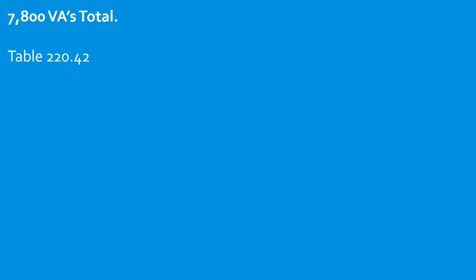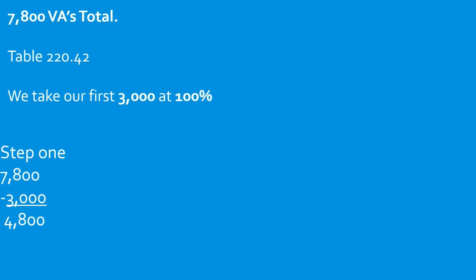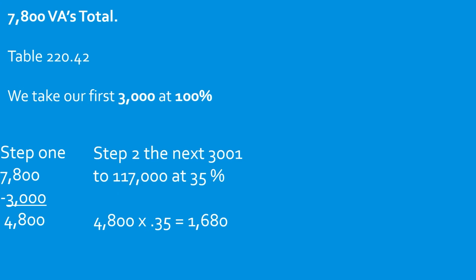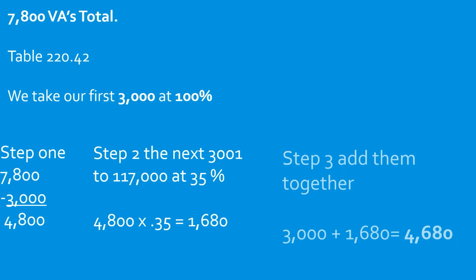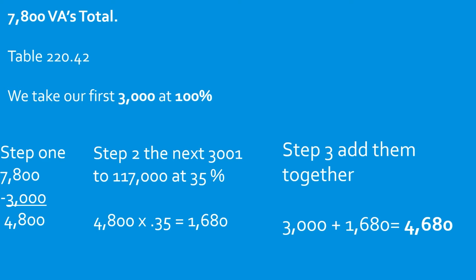Now we head to table 220.42. We take our first 3,000 at 100%. So we take our total minus 3,000, set it to the side. That's going to give us 4,800 VAs. Step 2, we're going to take the next section at 35%. So we take the 4,800, multiply it by 0.35. That is going to give us 1,680. Step 3, we just add back the 3,000. That is going to give us 4,680 VAs.